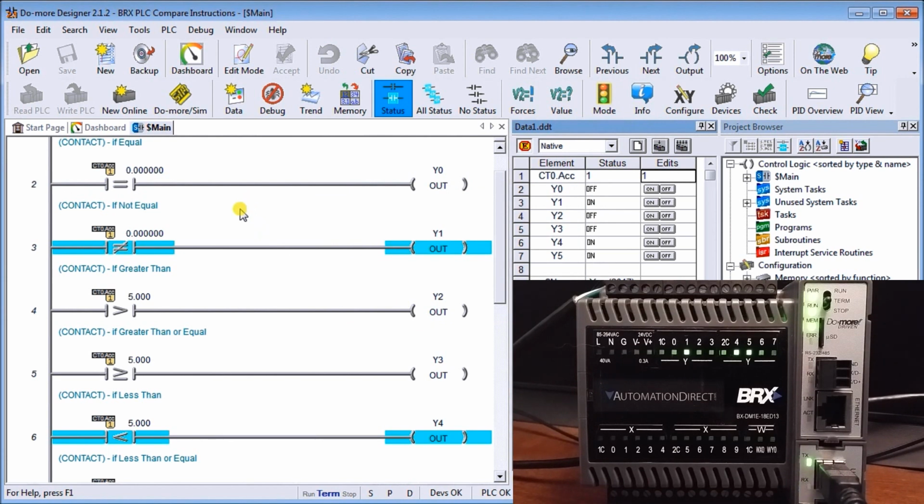Once we turn to 1, you'll notice that my contacts have now changed. And this is my not equal flag. So if it's not equal to 0, which is true, now I have Y1 that is activated. My Y4 and Y5 are still activated because they're still less than 5. So now let's move the counter value up to 4. And once I do that, you see that my status does not change.